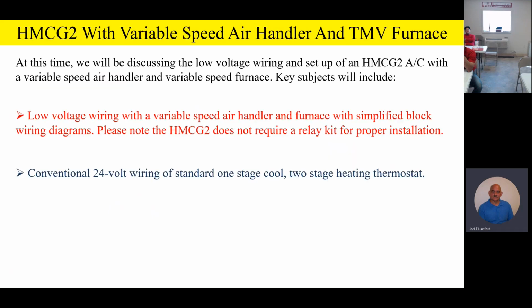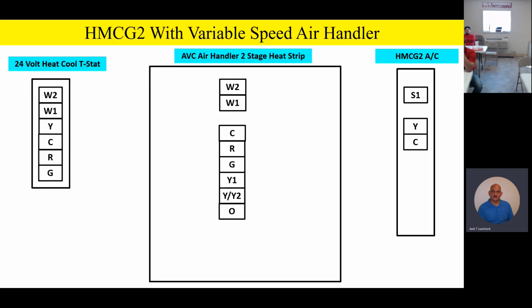Well, fellas, on the variable speed product, you still don't have to have a relay. Still 24-volt wiring. But you're going to notice now we've got this variable speed air handler that's going to be set up for air conditioning, not heat pump. So please make a note of this.